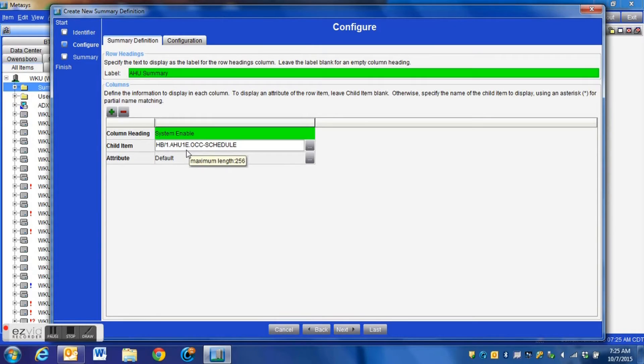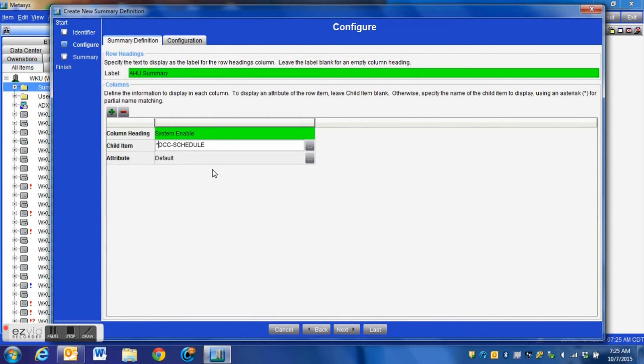Then we will delete out a portion of this that we do not need. What you want to do is only use portions of the name that are common to multiple controllers. So we just highlight that, delete it out, and we're going to replace that with an asterisk - we put one at the beginning and we also put one at the end. Now when you get into setting up a lot of these summary definitions, it might be a great time for you to go through the extra effort and standardize the naming on the points within your system.